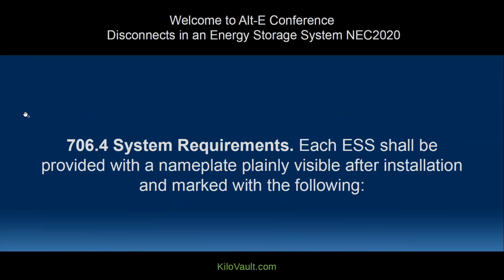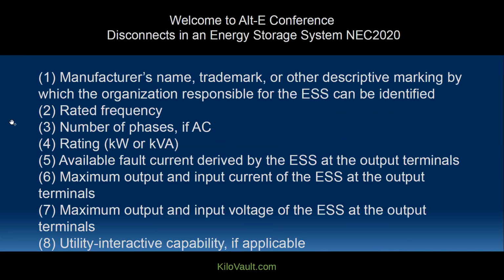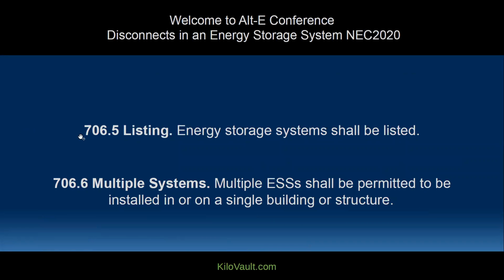System requirements. So: the manufacturer's trademark or something that identifies it to the manufacturer. If it's going to be an AC battery, the rated frequency and number of phases. For AC or DC, you're going to want your kilowatts or kVA, the available fault current, and the maximum output and input current of your energy storage, as well as your maximum input and output voltage. Utility interactive capabilities as well. Your energy storage should be listed, and this applies when there are multiple systems installed in one structure.